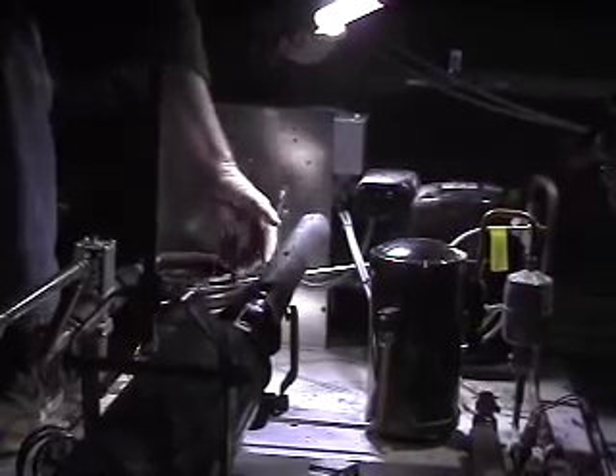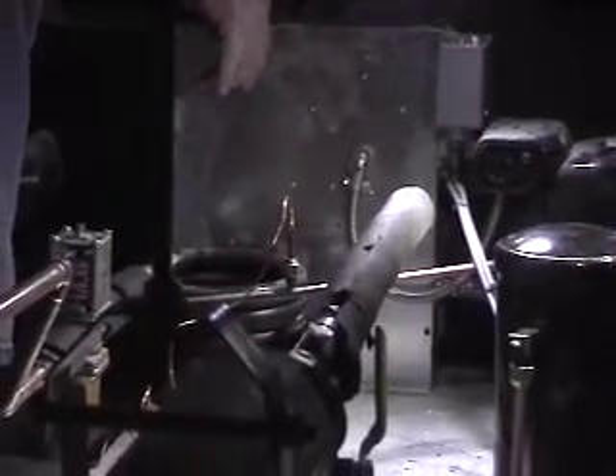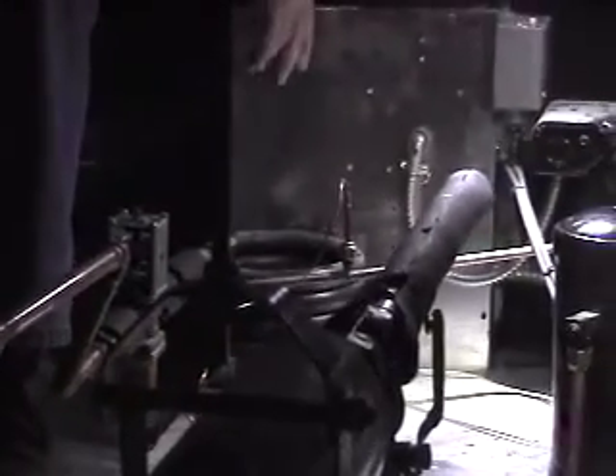But we have service valves, so if you ever need to take it off, you take the valve off very easily. Just so you know, there's a Schrader valve in here and a Schrader depressor in here. So if you had to replace that, you just take it off with very little gas loss. You don't have to worry about pumping it down or evacuating the system somehow. That's all taken care of for you.